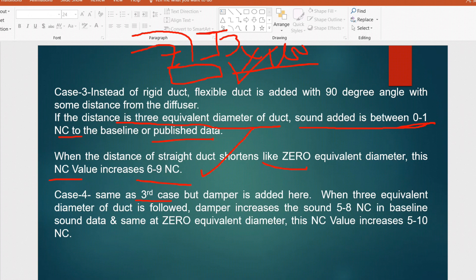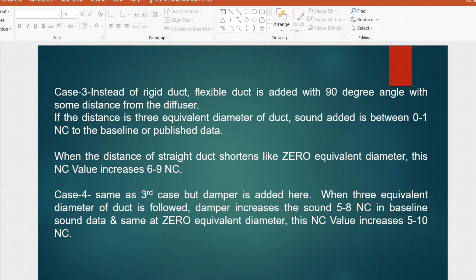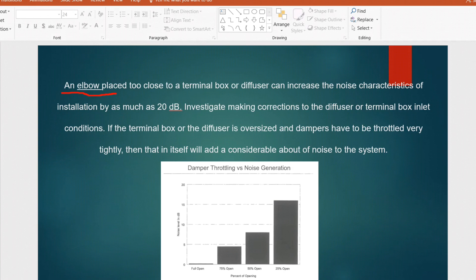In Case 4, same as Case 3 but a volume control damper is also added. When the 3 equivalent diameter distance is followed, the damper increases sound by only 5 to 8 NC. But if the equivalent distance is not maintained, the flexible duct with the damper will increase sound level by 5 to 10 NC. Due to site constraints, this is what happens in most cases, creating higher NC levels. Also, an elbow placed too close to the terminal box or diffuser can increase noise by as much as 20 decibels.